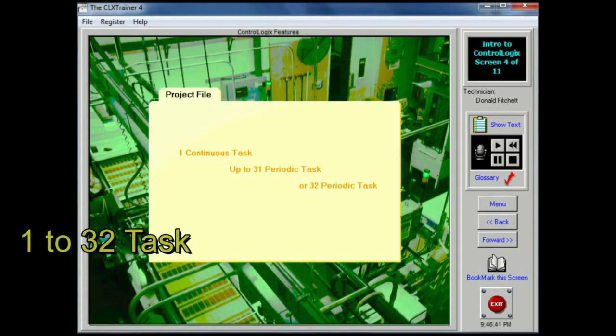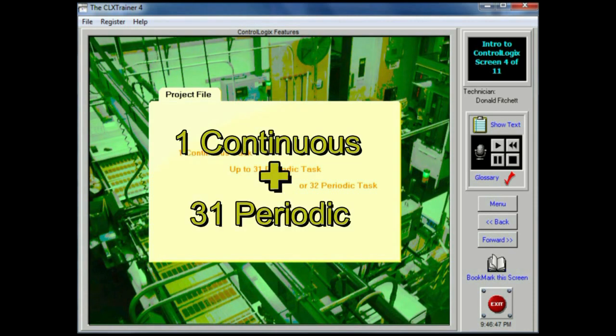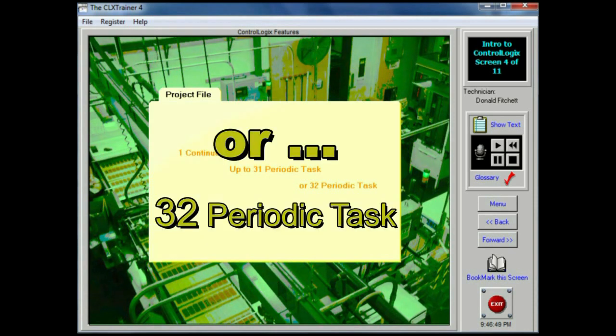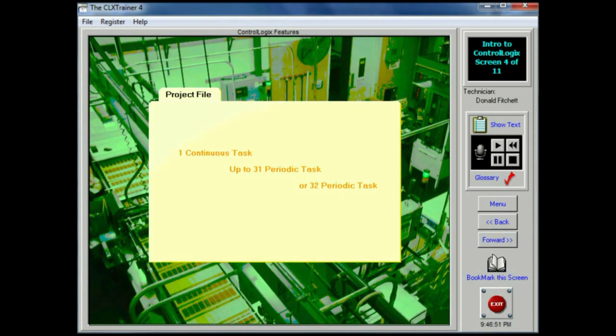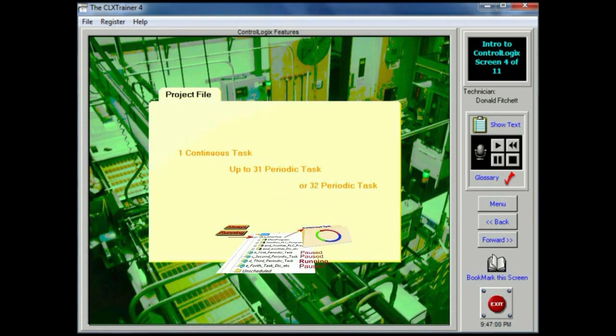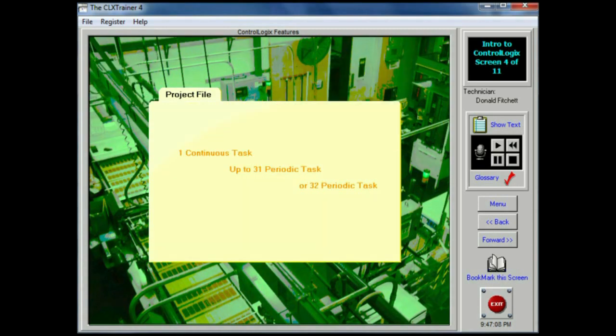Multitasking, multi-discipline. This feature allows the controller to handle up to 32 tasks — one continuous and up to 31 periodic, or simply 32 periodic. A task provides priority and scheduling information for a set of one or more programs that are executed based on a specific set of criteria. These tasks operate as interrupts so that the controller will suspend execution of the current task to perform the task being called. Each individual task can schedule up to 32 programs.